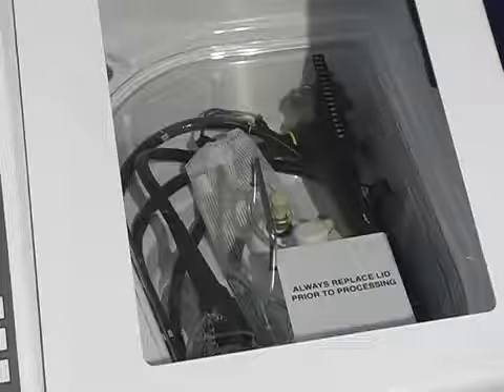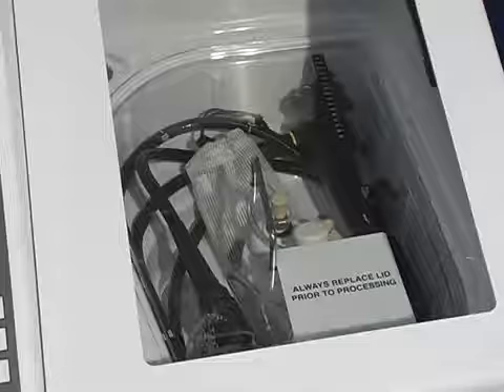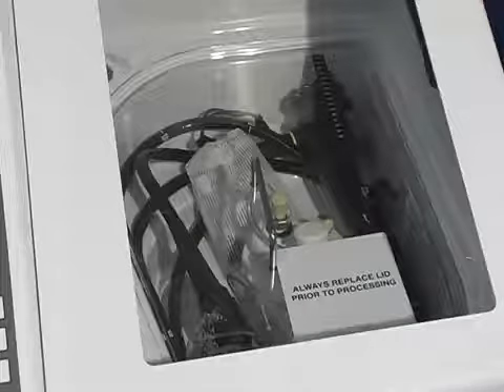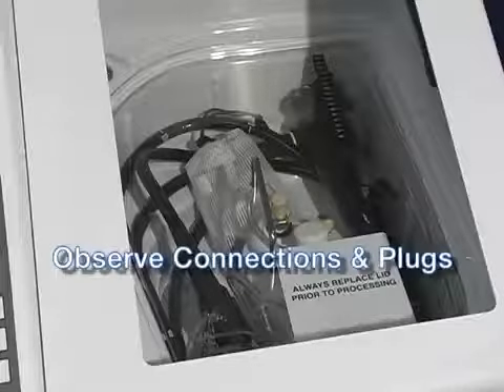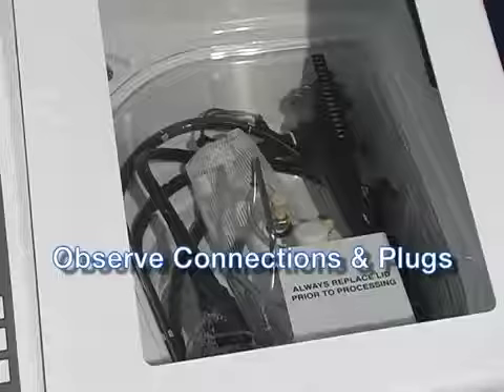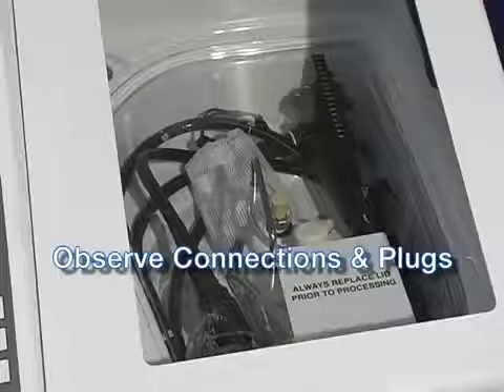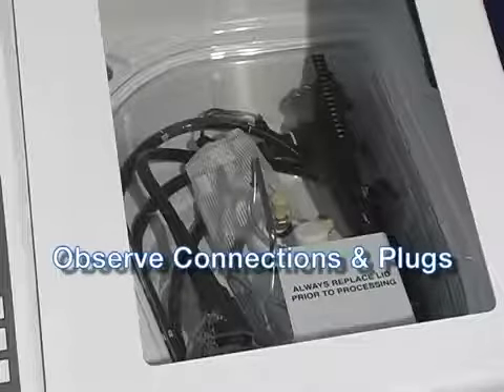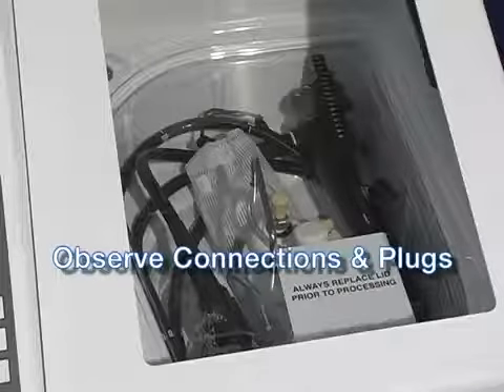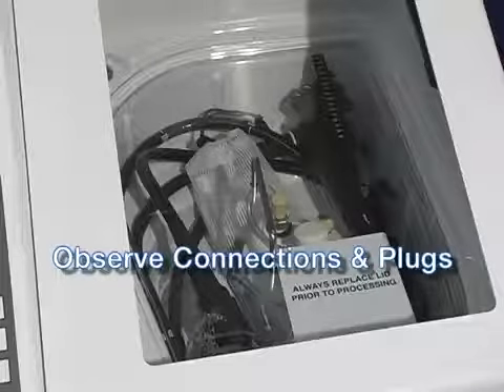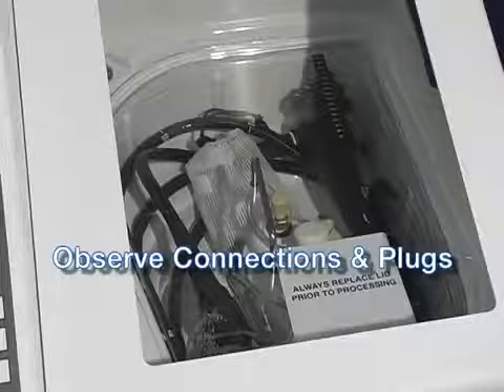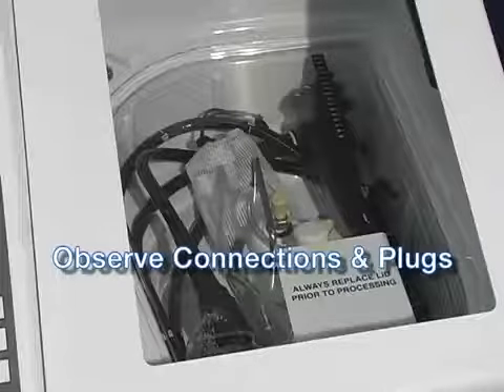The first operation is the flush cycle, unless you have a DSD-201 with leak tester. With the leak test option, the first step is the inflation and monitoring of the scope, which lasts approximately 40 seconds. Then the flush cycle begins. During the first part of any cycle, carefully observe the endoscope connections for leaks. The stainless steel channel plug in the control section is designed to permit the passage of small amounts of fluid.